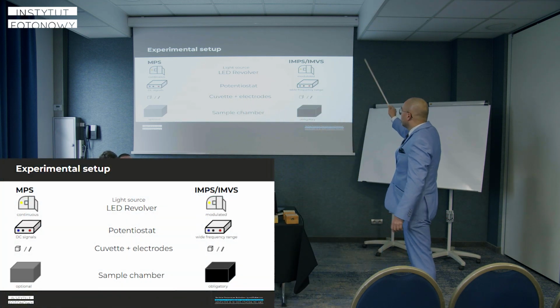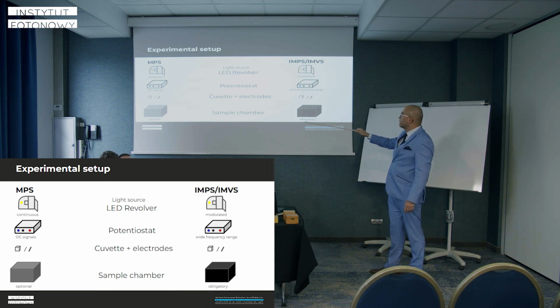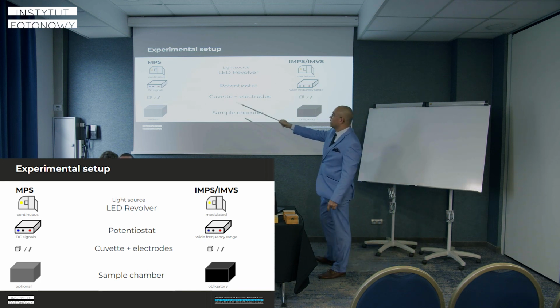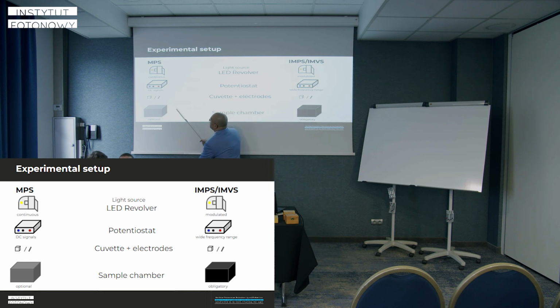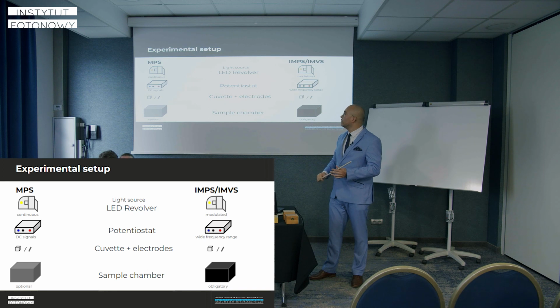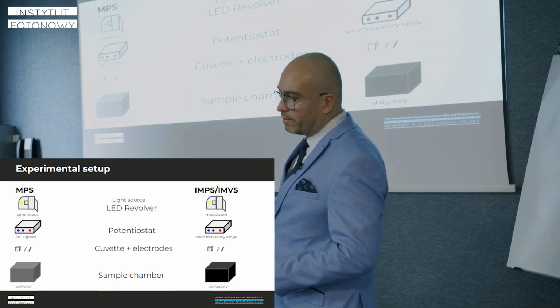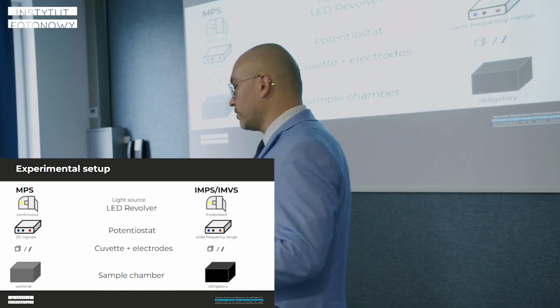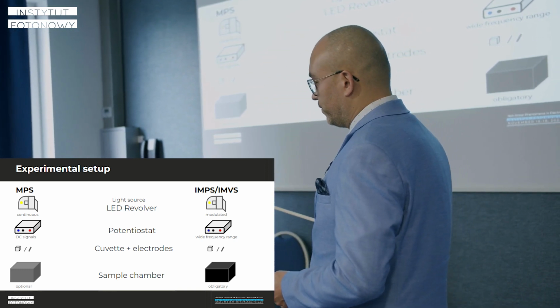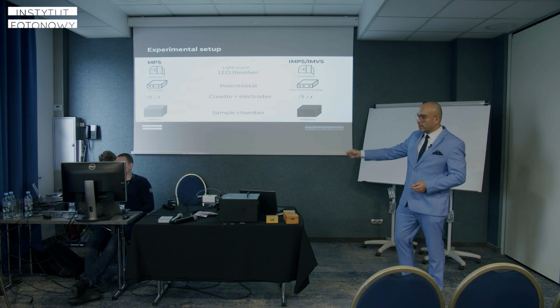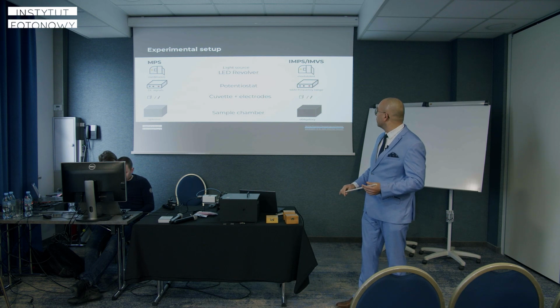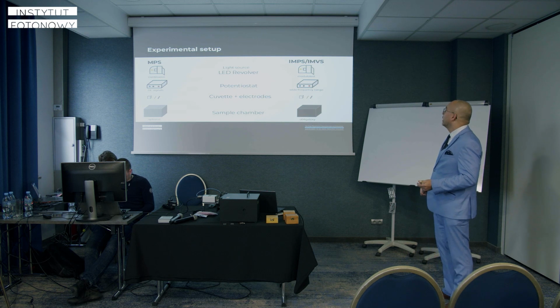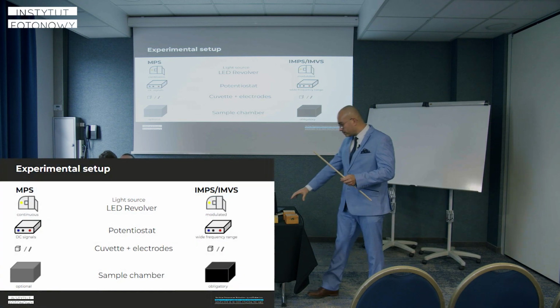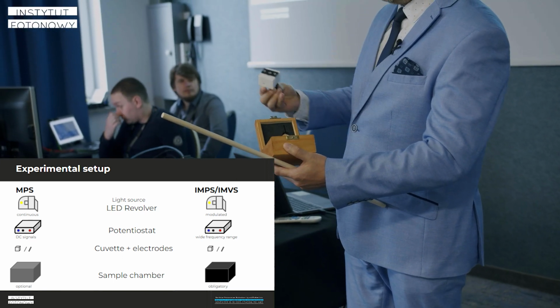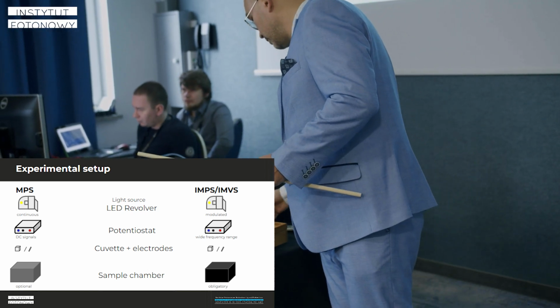This is because we measure here alternating signals in a wide frequency range, and these two setups are configured in a different way. Here we only measure stationary signals, so the setup is configured to be not sensitive to AC signals, and then we have to take care to screen the sample or just cover it with a box to protect it from external light. But in this case, we need a Faraday cage to screen off all stray fields and electromagnetic noise and so on. And of course, a cuvette. Our cuvette we just hang on the cage and in the set of electrodes.